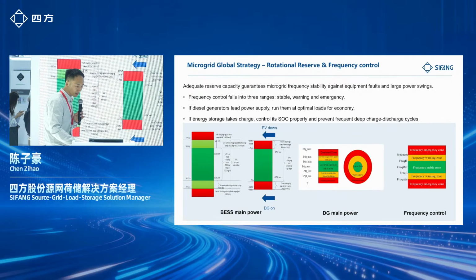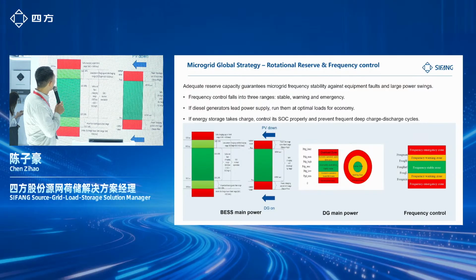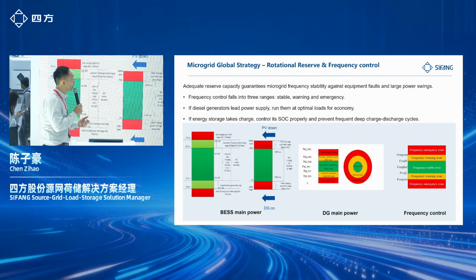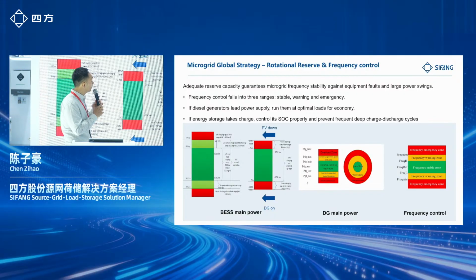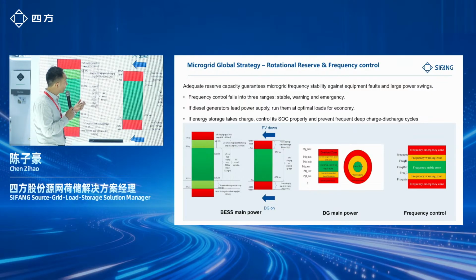And here's some typical strategies we already applied in our controller. The first one is the rotational reserve. We keep enough reserve of the whole system to make sure any small changes in this system can be handled and achieve the stability of the system. And the frequency control normally falls into three ranges: the stable zone, warning zone, also the emergency zone. And based on the status of the system, we apply the different strategy.